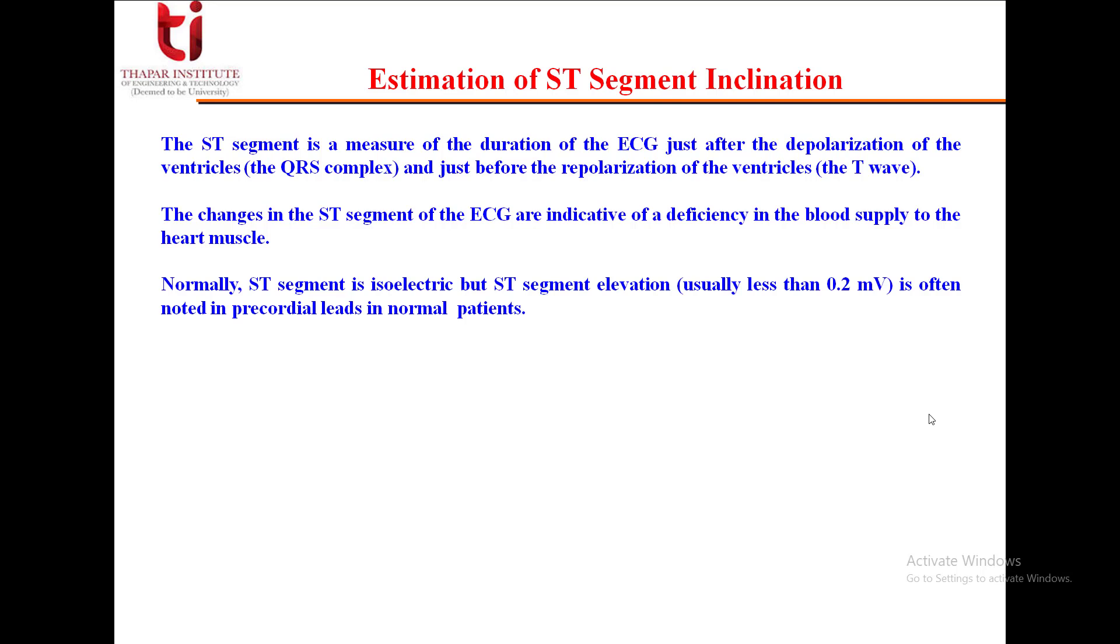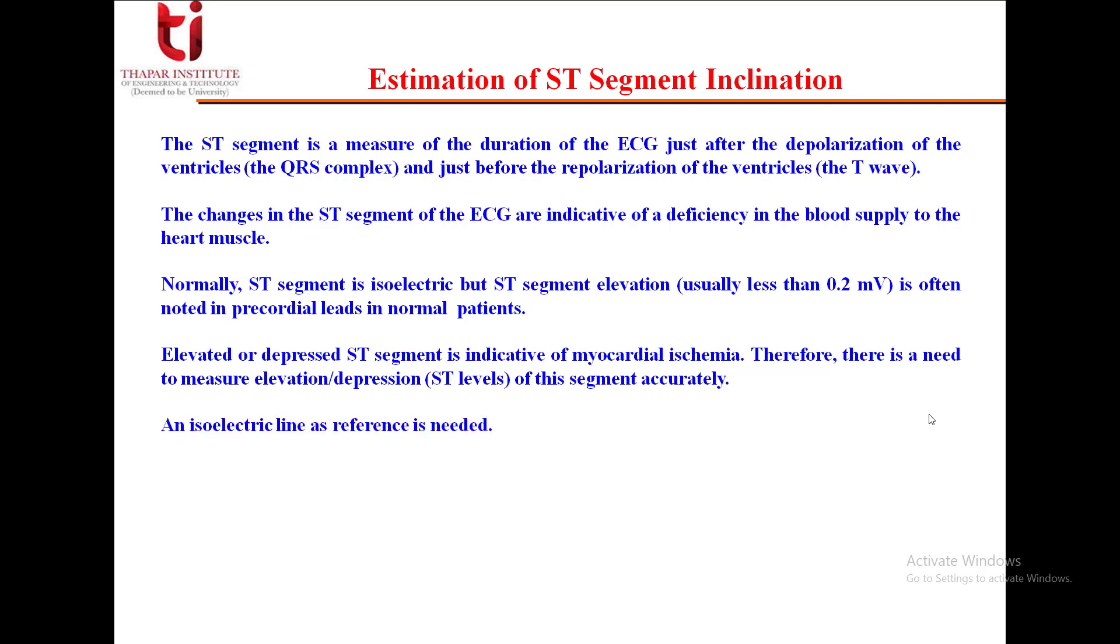Normally, this ST segment is isoelectric, but ST segment elevation, usually less than 0.2 mV, is often noted in precordial leads in normal patients. Elevated or depressed ST segment is indicative of myocardial ischemia. Therefore, there is a need to measure elevation or depression, the ST levels of ECG segment, accurately. An isoelectric line as a reference is required.